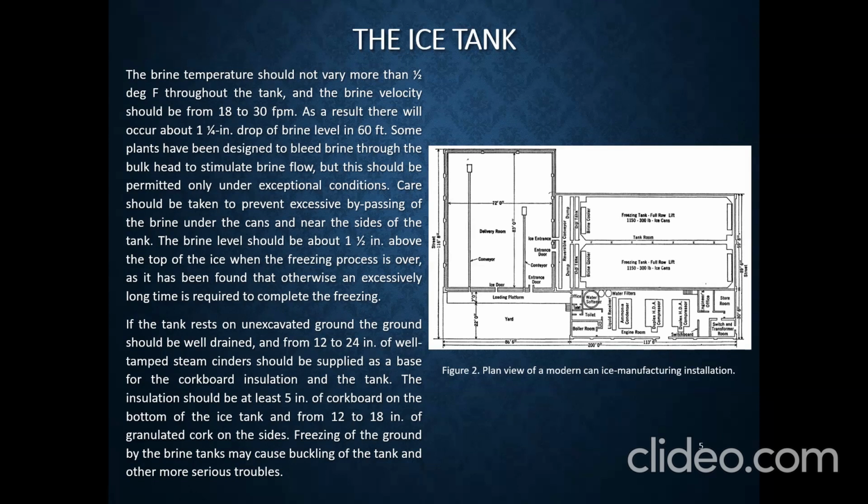Some plants have been designed to bleed brine through the bulkhead to stimulate brine flow, but this should be permitted only under exceptional conditions. So care should be taken to prevent excessive bypassing of the brine under the cans and near the sides of the tank.